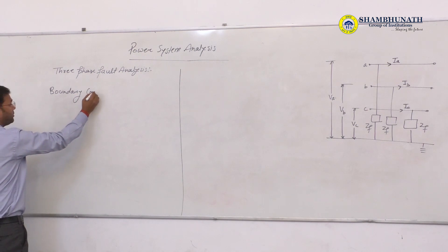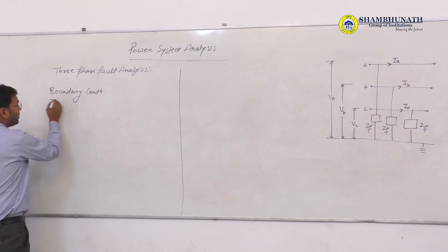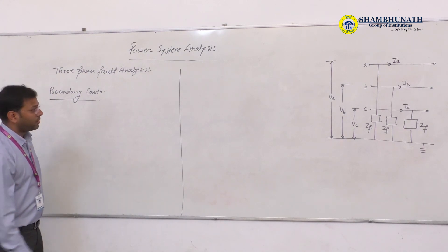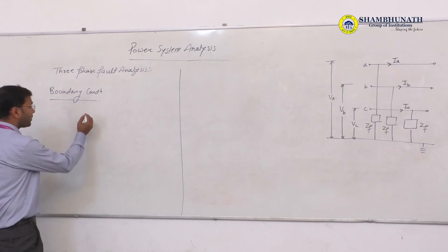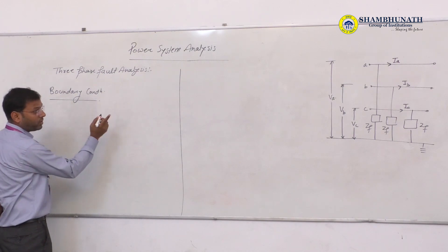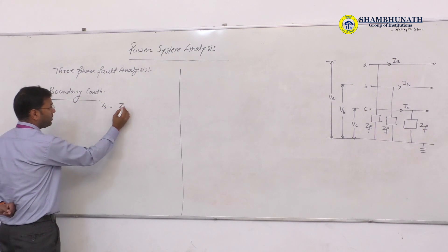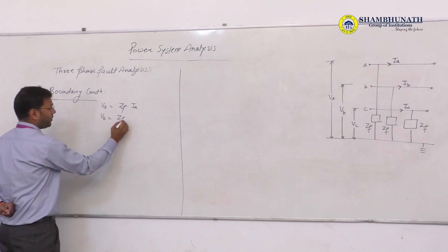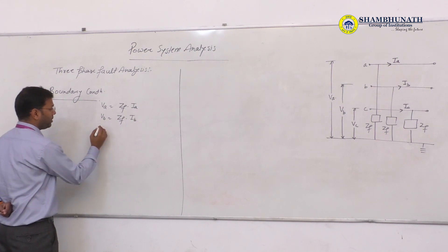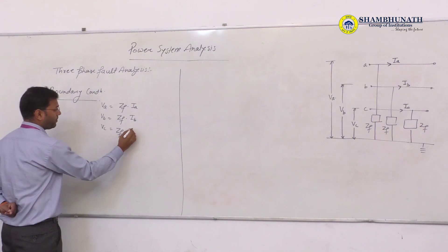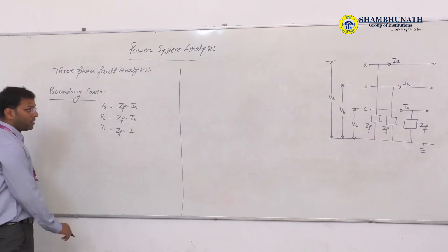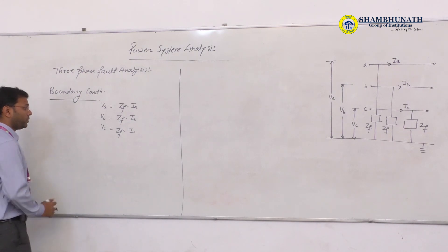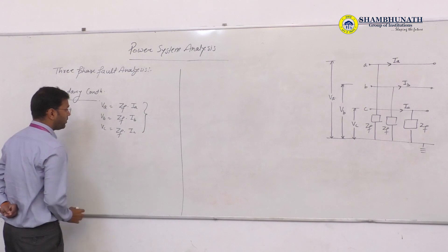Boundary conditions: The boundary conditions of 3-phase fault analysis. We see that in terms of voltage: VA equals ZF into IA, VB equals ZF into IB, and VC equals ZF into IC. And the current condition is IA plus IB plus IC equals zero. These are the boundary conditions in terms of voltage.